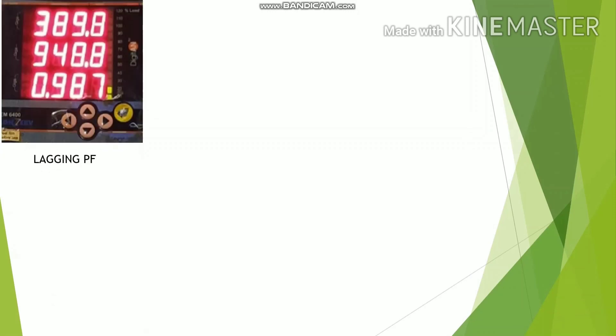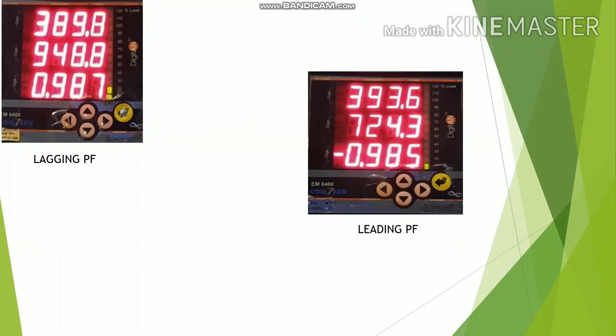Now I will show you some examples of leading, lagging, and unity power factor. The first one is lagging power factor. In this energy meter, it is showing lagging PF, which is less than unity. That means the inductive load inside the system increases. Second one is the leading power factor. Leading power factor is denoted with a negative sign. That means capacitive load inside the system increases.